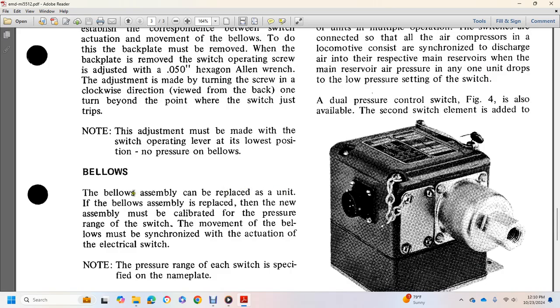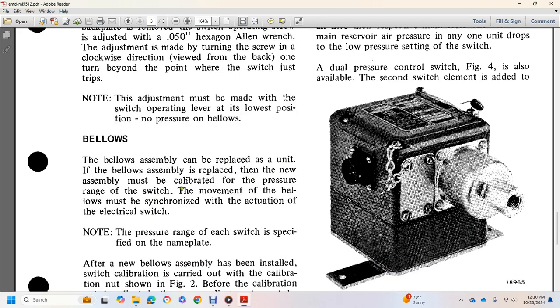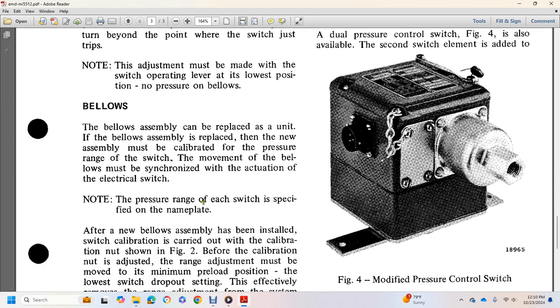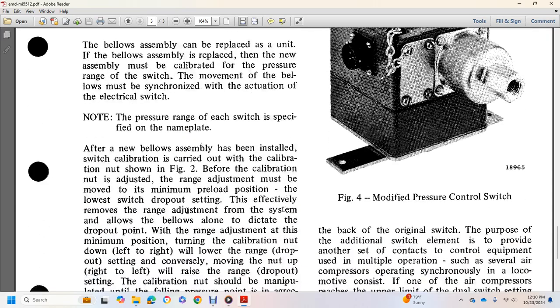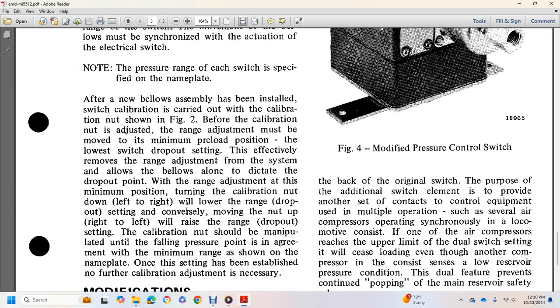Bellows assembly may be replaced as a unit. The bellows assembly is replaced with a new assembly calibrated with the pressure range switch. Movement of the bellows must be synchronized with the actuation of the electrical switch. Note that the pressure range of each switch is specified on the nameplate. After the new bellows has been installed, switch calibration is carried out with the calibration nut shown in Figure 2, and then with the calibration nut adjusted.